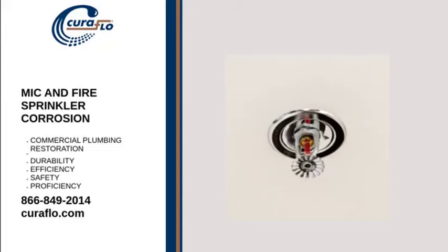MIC sources. Although MIC has been present in fire protection systems for a long time, the corrosion source was only identified recently. The results are not conclusive, but it is thought that MIC is mainly caused by microorganisms with acid-producing bacteria or sulfate-reducing bacteria that are found in water sources. NFPA standards specify that environmental conditions and water supply should be evaluated to determine if conditions and microbes that contribute to MIC exist. What is interesting is that MIC does not only occur in wet pipe systems, but also in dry systems.